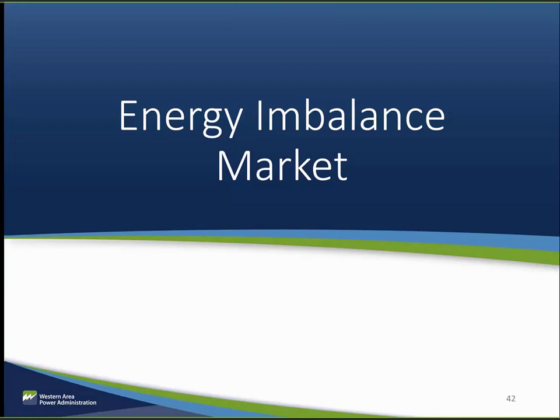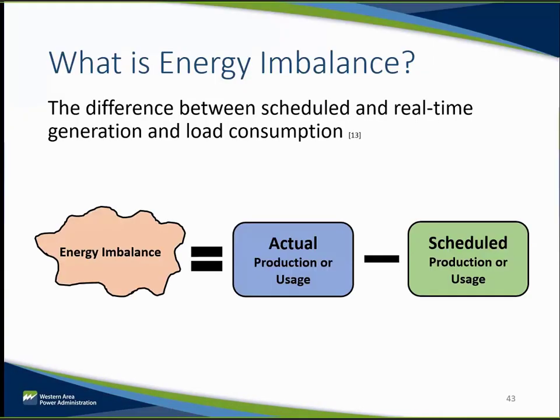The next construct we will discuss is the energy imbalance market construct. This construct has been used in the eastern interconnection and is currently becoming more prominent in the western interconnection. With an energy imbalance market, the underlying bilateral market construct remains, but an extra layer is added to allow the market operator to adjust for the differences between scheduled production and usage and actual production or usage in real time using security-constrained economic dispatch.